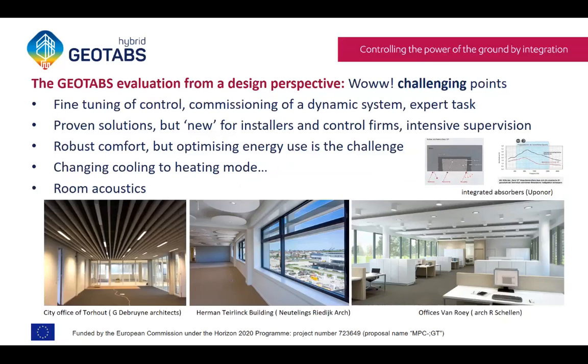Good, we still have other challenges. I'll go a bit more quickly so we have time for solutions too. One of them is fine-tuning the control. We have a slow reacting system, the TABS. It has a self-regulating effect, but to find the right heating and cooling curves for the control setup, you need dynamic thinking. You need to look at graphs — this is quite an expert task and takes a long time, so it's an effort for the designer again.